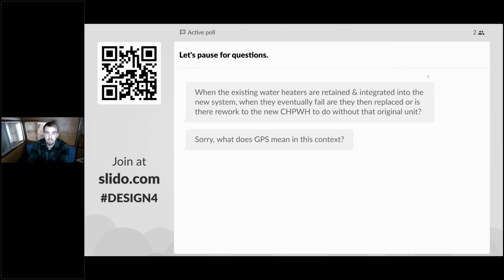or temperature maintenance heating than we need with the remaining 2 heaters, but we do have less redundancy at this point. So at that step in the process, it would be up to the owner to decide, am I comfortable enough with this heat pump water heating equipment? Have I had good luck with it to rely on it to be able to cover the heat that it has been covering this entire time? Or do I want to replace that last electric heater and maintain full redundancy in case anything goes down?